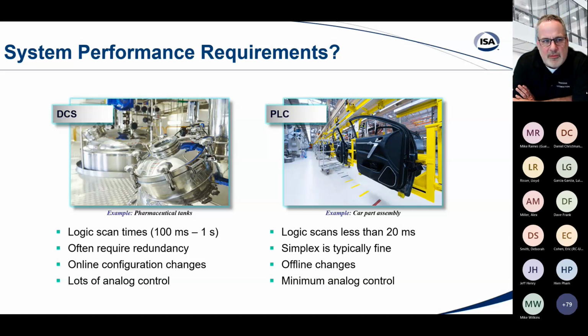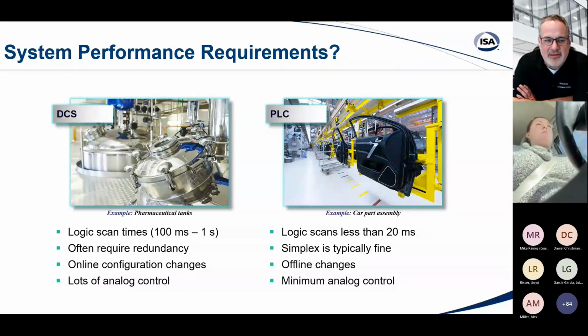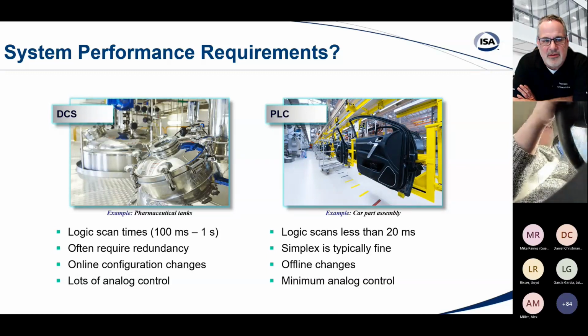As far as system performance requirements go, on the DCS side, we're not typically as worried about high-speed requirements. We're typically at the 100 millisecond to 1 second operation, whereas a logic scan for a PLC might be less than 20 milliseconds. So they're very quick. I mentioned before the redundancy requirements. DCS often requires redundancy, as well as the ability to make online configuration changes. Again, we can't stop the process. So if one of the triplicated transmitters has failed out in the field, you've got to replace it, but maybe it's a different type of technology. You need to adjust the configuration to accept that new device while you're online.